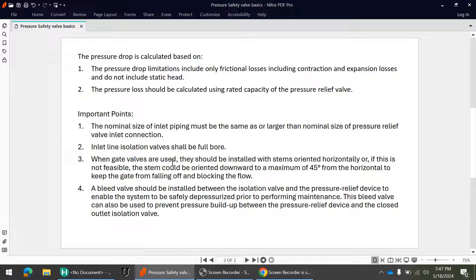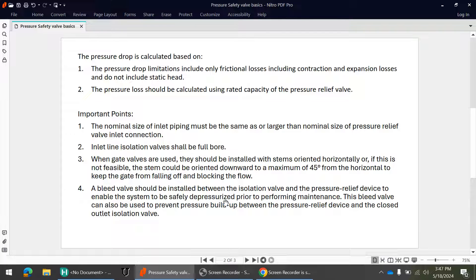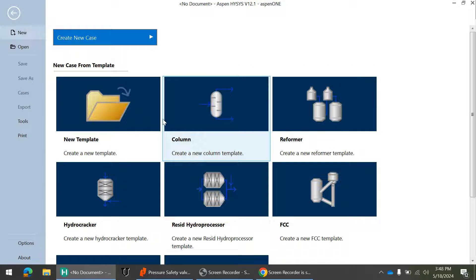The inlet line isolation valve shall be full bore — you cannot use a reduced bore valve for isolation in the inlet line. If using gate valves for isolation, they should be mounted horizontally; if not feasible, they can be oriented downward to a maximum of 45 degrees from horizontal to prevent the gate from falling and blocking flow. A bleed valve should be installed between the isolation valve and the pressure relief device to enable safe depressurization for maintenance.